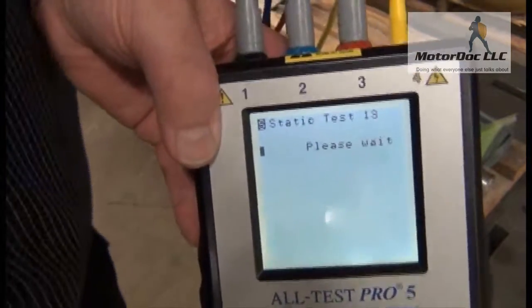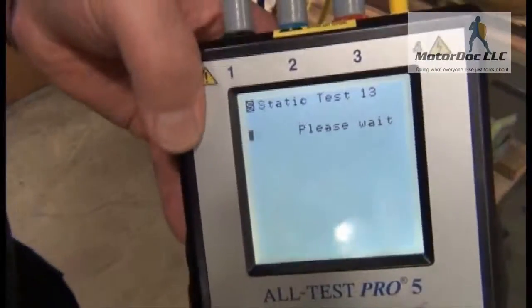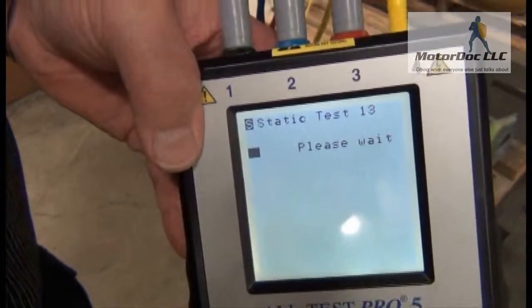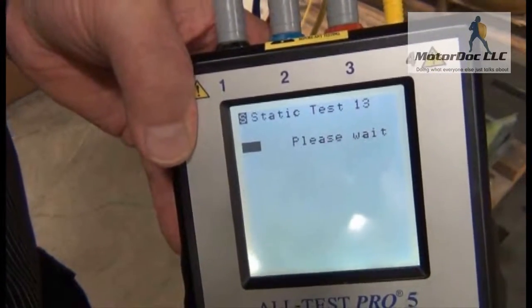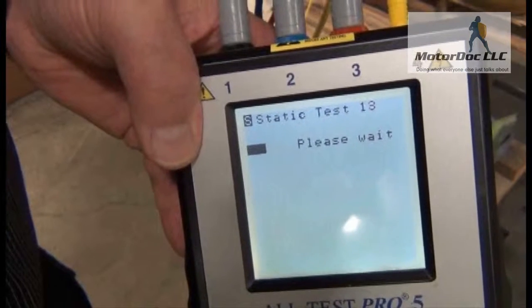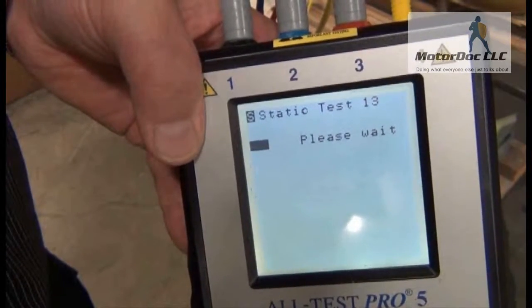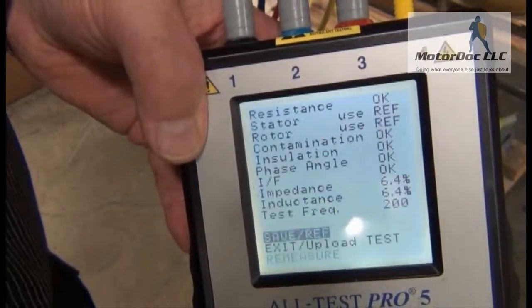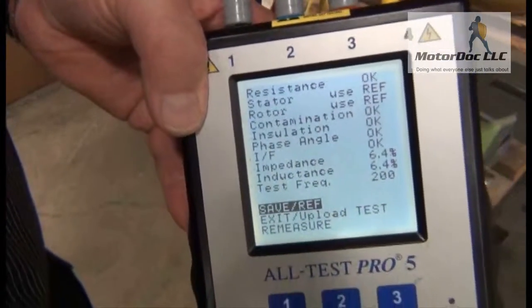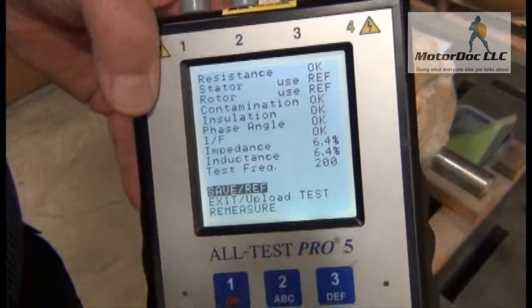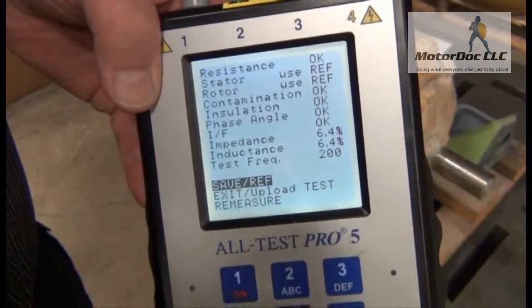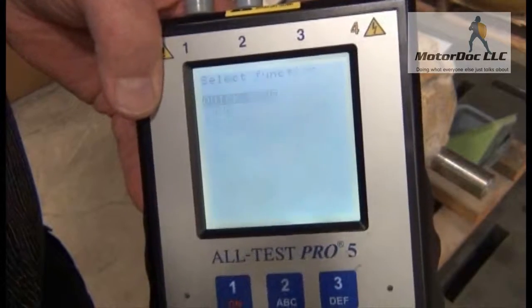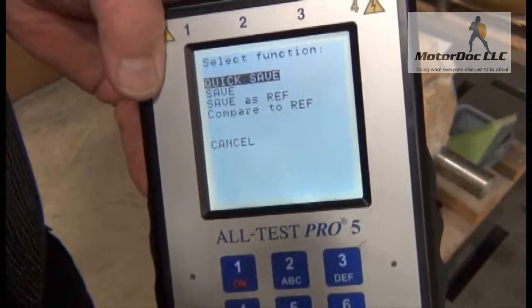This is not quite as long as paint drying unless it's a very quick dry paint. It goes very very rapidly and within a couple of minutes I'm going to have a complete idea of the condition of this winding. There I go, it says everything's okay, the reference value as well. So the next thing I want to do like we talked about before is save.